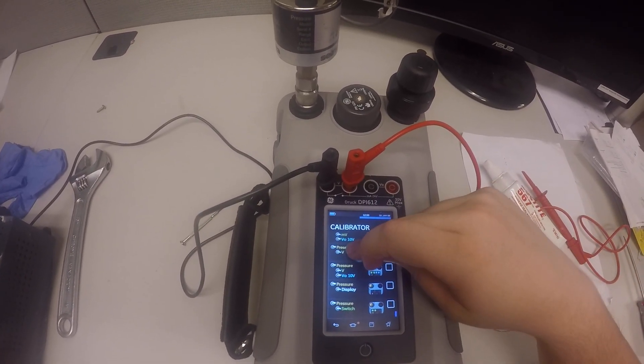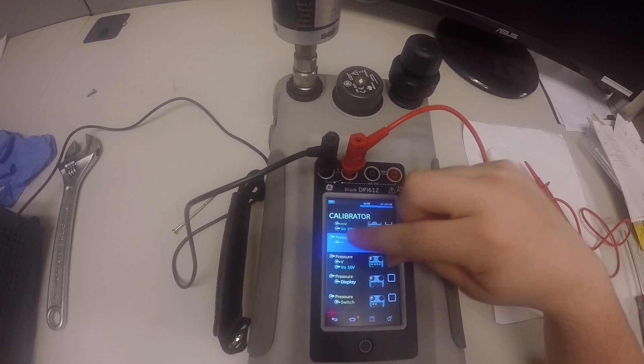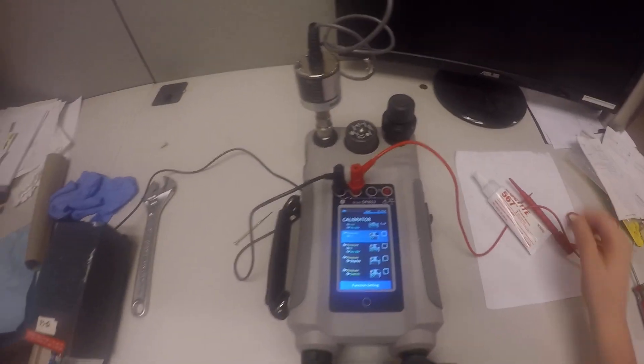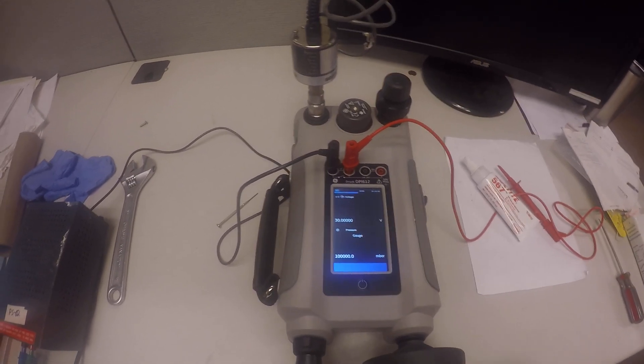The volt output 10 volts selection is for when you're using the Druck output to power your transducer. You can only do this when your transducer takes an excitation voltage of 10 volts or lower. In this case, this transducer has an excitation voltage above that, so we're going to use just measure volts. Now we've selected that — it takes a little bit to load.